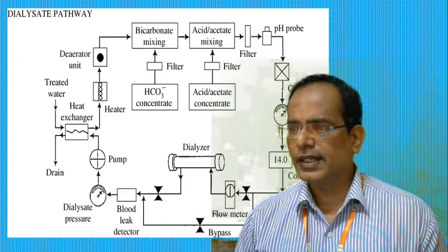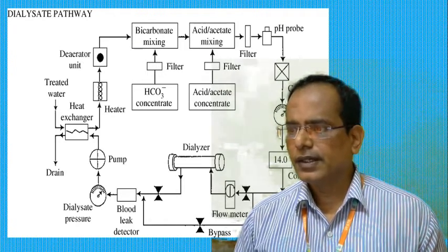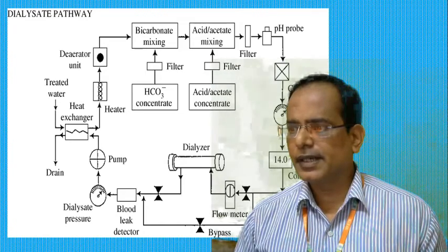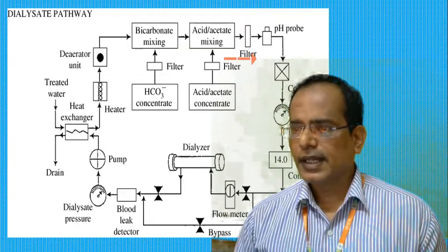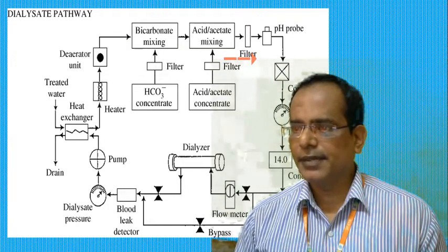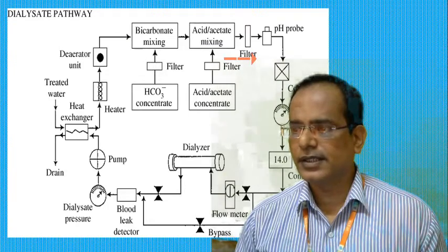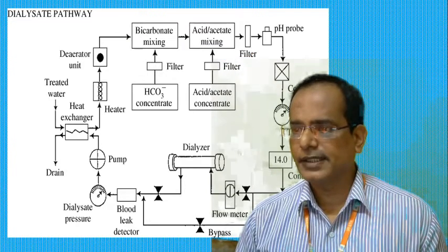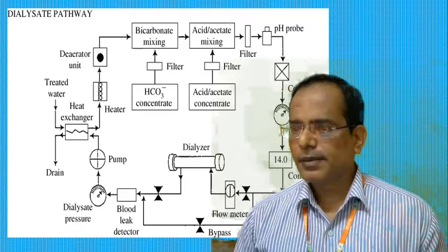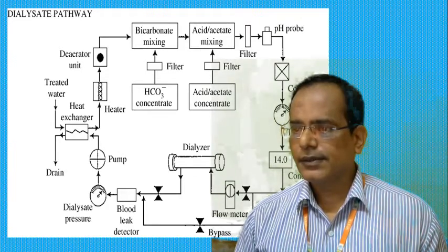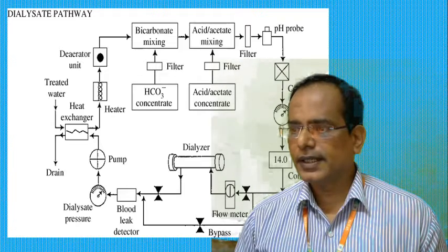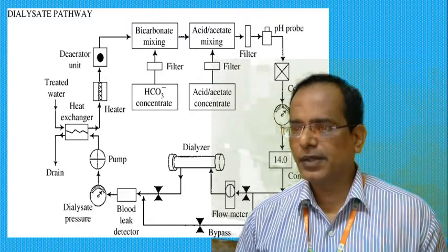Thus, by measuring the conductivity of the mixing chamber with the help of an instrument, we can find any major abnormalities in the concentration of the dialysate. Before the dialysate enters the dialysis chamber, we have to monitor for these abnormalities.